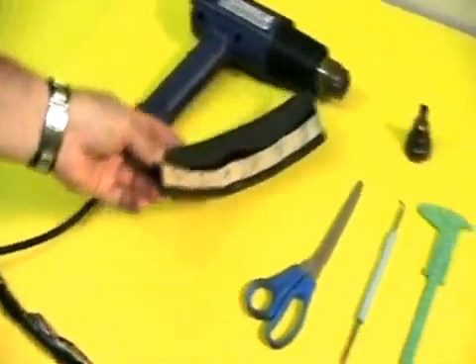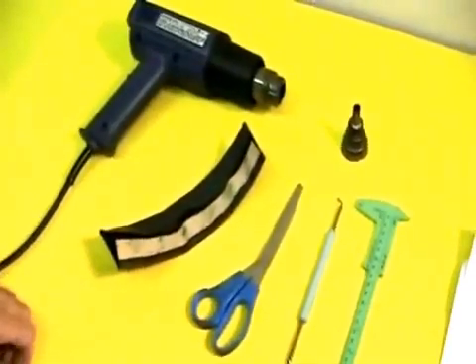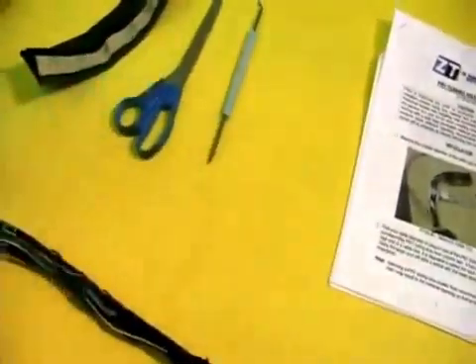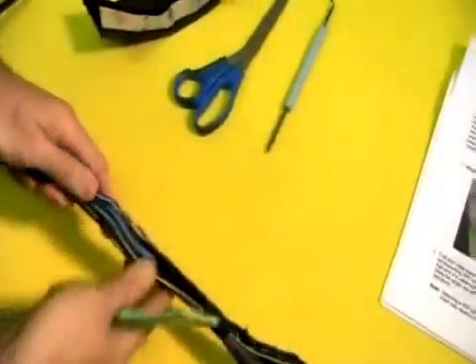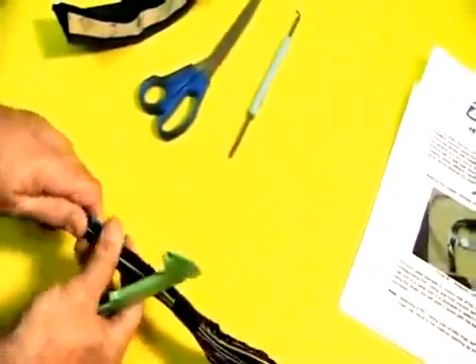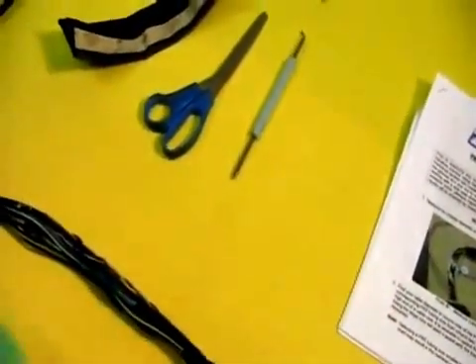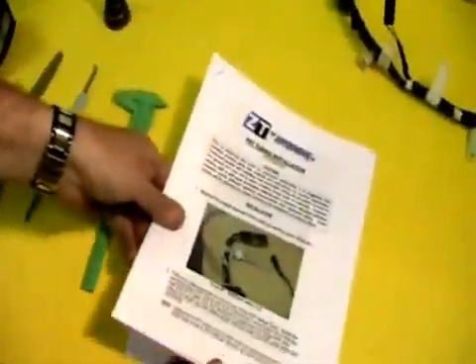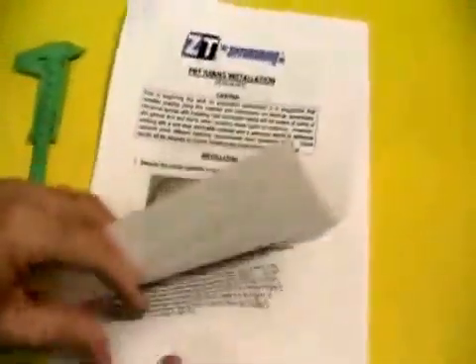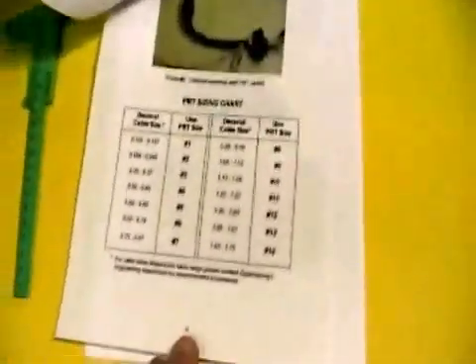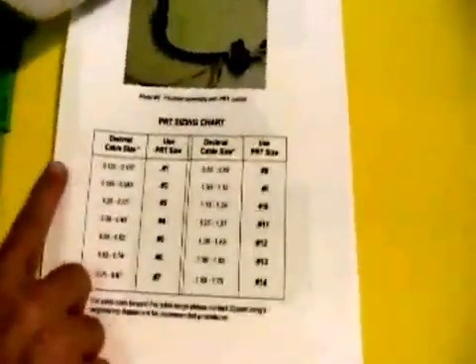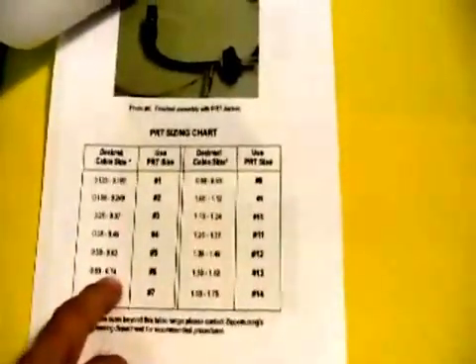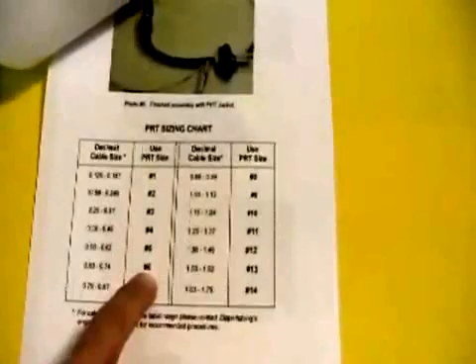The first thing you're going to do when making a PRT installation is to measure the cable diameter that you have. Now I've already done that. This cable when compressed is right around 5 eighths of an inch. It's important that you measure the diameter because what you want to do is go to the sizing chart and find the cable diameter. In this case, 5 eighths to 3 quarters is a number 6 size.